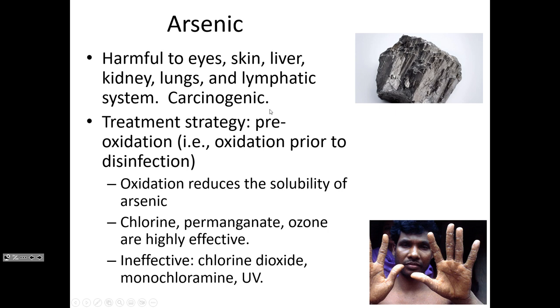Arsenic, when it's reduced, is soluble; when it's oxidized, it's less soluble. Arsenic can be found in four different charges, and the least soluble is arsenic 5+. Oxidizing arsenic with chlorine, permanganate, or ozone will allow it to precipitate out and be removed in the settling and filtration stages.